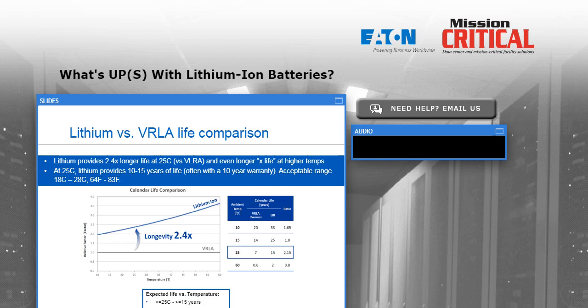Here is a vendor's description comparing service life, and this is one of the big advantages. With valve-regulated lead-acid batteries, we've always budgeted for replacement every 5 years. You might get 6 years or a little more in a typical UPS application, but that was the exception rather than the rule.